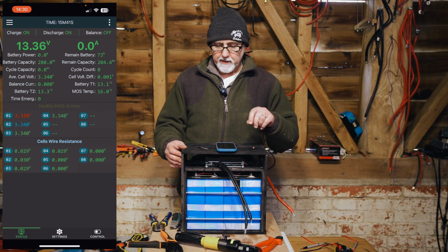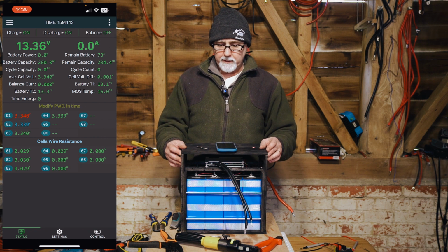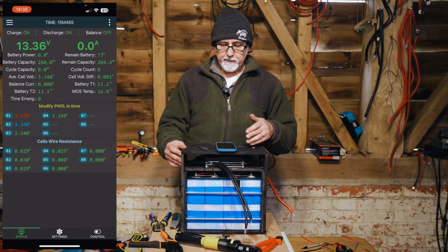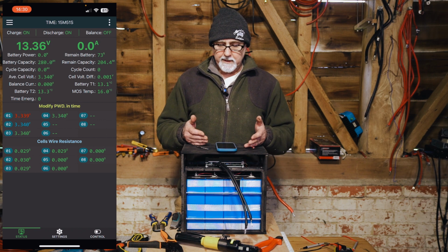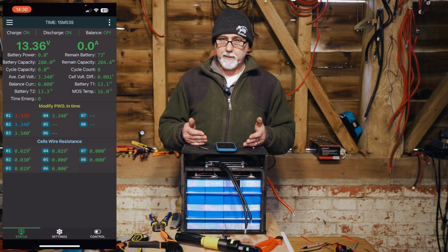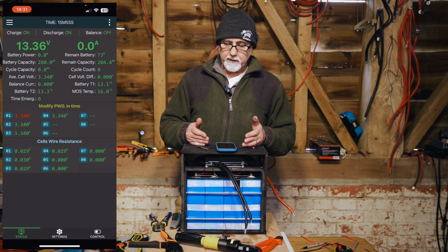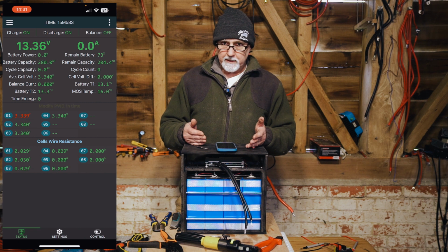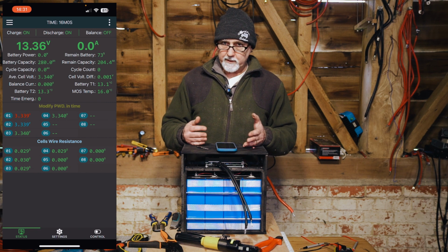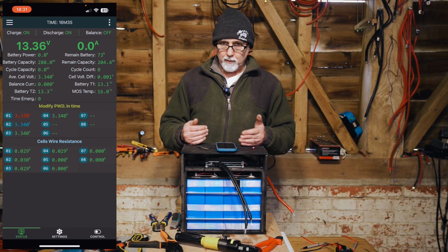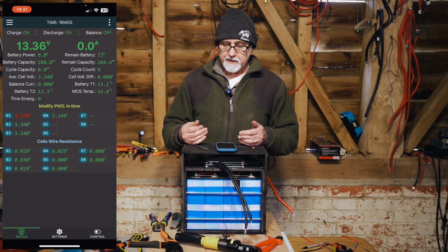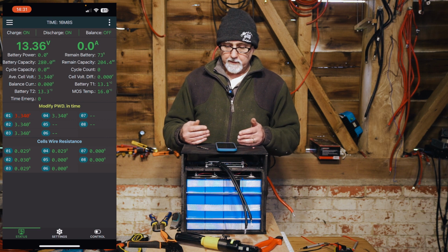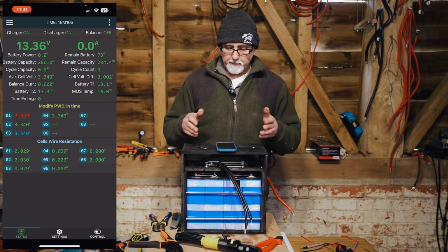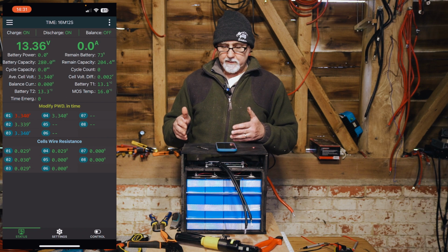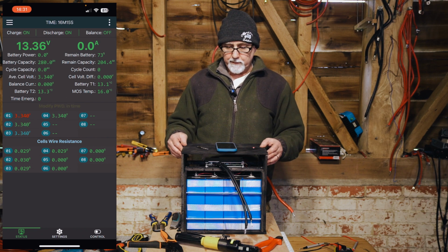As we can see, the difference at the moment is just 0.001, so these cells are being kept well in balance by the BMS and we don't need to worry about top balancing. If you're installing a BMS with passive balancing, or setting very strict parameters that give only a small window for the BMS to balance, you may need to consider top balancing. But in this case, with this BMS's default balancing parameters, these four cells will stay very closely matched.